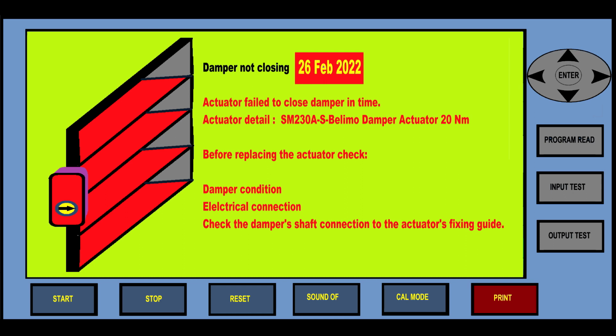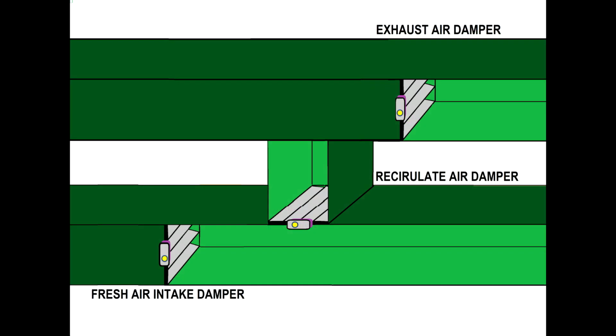Also, the PLC will pick up the fault and it will tell you which damper you have to replace and when it was broken, and so on. This is an air handling unit. You won't see the heat exchangers and anything. You see this exhaust damper and fresh air intake damper are opening while the recirculated air damper is closing. Guys, you always have to maintain the minimum open area for the supply fan to drag the air. So they work against each other: the exhaust air damper and fresh air intake damper work together against the recirculated air damper, because if you bring more air into the premises, you have to exhaust more air and so on.